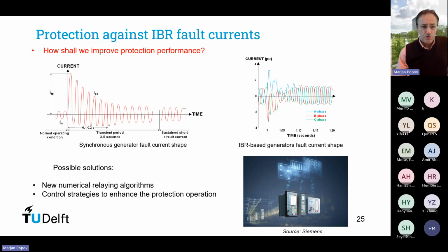I will now move on shortly to the next important topic, which is protection against IBR, inverter-based resources, fault currents. Whilst in classical systems we have synchronous generators in which the fault current shape is quite determined, with large amplitudes that last for a longer period of time, and subtransient, transient, and steady state components, in the future, IBR-based generator faults will be quite different. They will not have such high amplitudes and they will be damped much faster.